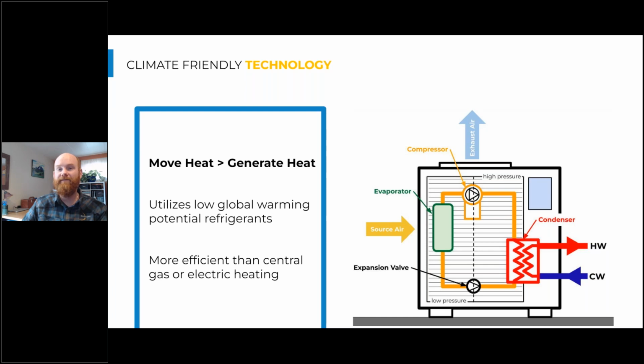And so this process is really efficient. It's typically about 300% efficient, a COP, coefficient of performance, of 3, which is 3 times as efficient as an optimized electric resistance water heater and over 3 times as efficient as a gas water heater, as those are typically operating closer to around 85% efficiency, where this is 300%. So it's a much more efficient technology than a gas or electric resistance water heater. This technology has been around for decades and is fairly common in a lot of European and Asian markets for domestic water heating. But unfortunately, the US has been a little bit behind on the water heating aspect. And so we are just starting to implement this technology in our built environment, but it is a worthwhile technology to utilize for our future.